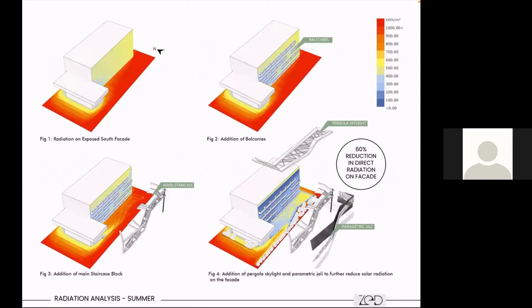We did insolation analysis to understand how we can further reduce the radiation impact, because direct and diffuse radiation impacts at least 30 to 40% of the cooling load. By designing balconies on the south, we were only able to reduce radiation on some parts of the building, but the horizontal surface was still receiving very high radiation. We further introduced the social staircase along with a pergola and a parametric skin blanketing the building, which reduces direct and diffuse radiation on the south and north facade by almost 60% on vertical surfaces and 40% on horizontal surfaces, creating a very favorable microclimate outside and decreasing the demand for enhanced cavity or insulated walls.